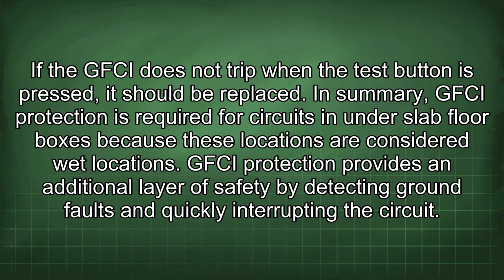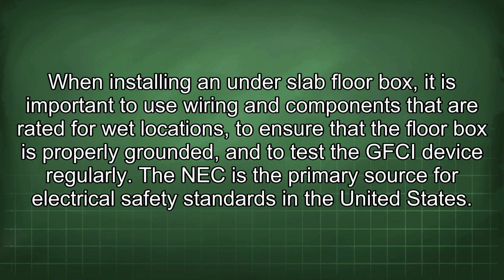In summary, GFCI protection is required for circuits in under-slab floor boxes because these locations are considered wet locations. GFCI protection provides an additional layer of safety by detecting ground faults and quickly interrupting the circuit. When installing an under-slab floor box, it is important to use wiring and components that are rated for wet locations, to ensure that the floor box is properly grounded, and to test the GFCI device regularly.